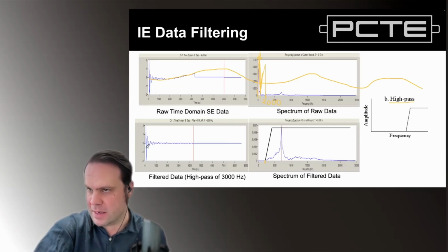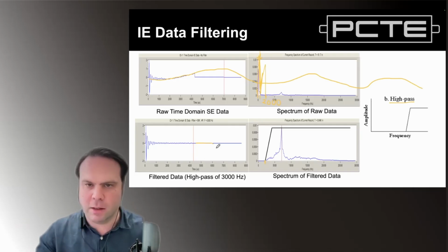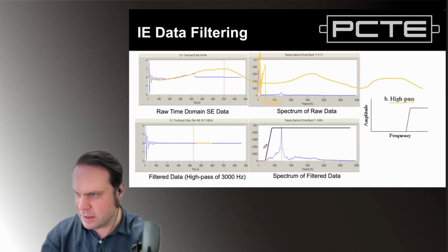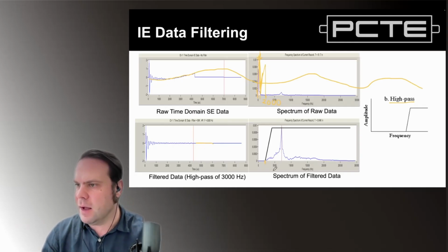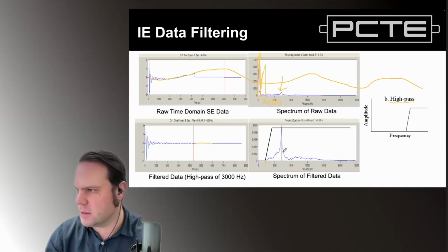And now that oscillation has been flattened out. It remains locked on 0, and our signal attenuates back to 0, returns to 0 after the energy is applied to the test. And we can also see that we now have this tiny little frequency response here on the previous chart, which is now clearly the result of our test.